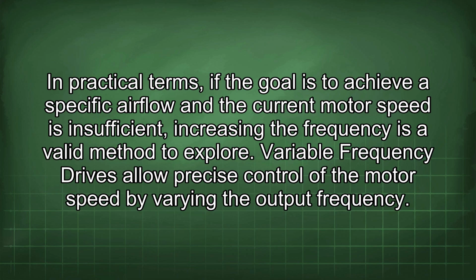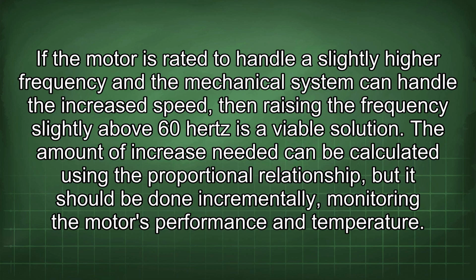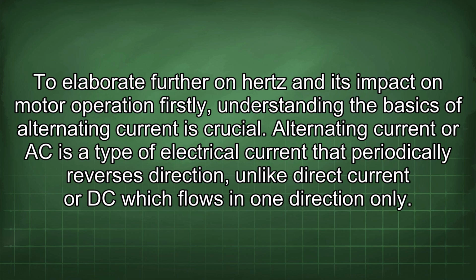In practical terms, if the goal is to achieve a specific airflow and the current motor speed is insufficient, increasing the frequency is a valid method to explore. Variable frequency drives allow precise control of the motor speed by varying the output frequency. If the motor is rated to handle a slightly higher frequency and the mechanical system can handle the increased speed, then raising the frequency slightly above 60 Hz is a viable solution. The amount of increase needed can be calculated using the proportional relationship, but it should be done incrementally, monitoring the motor's performance and temperature.